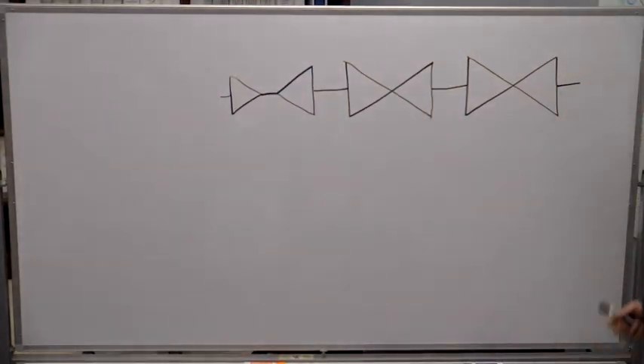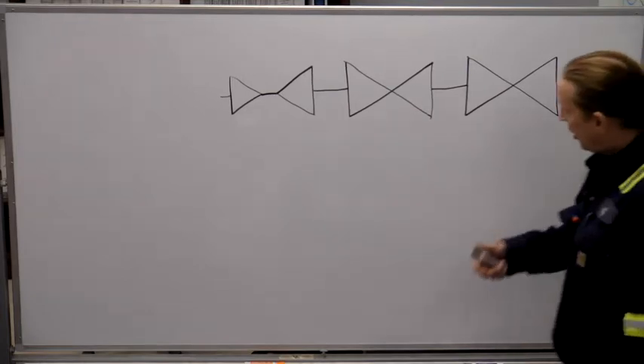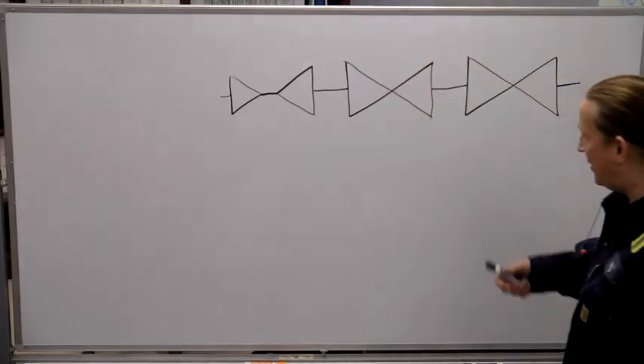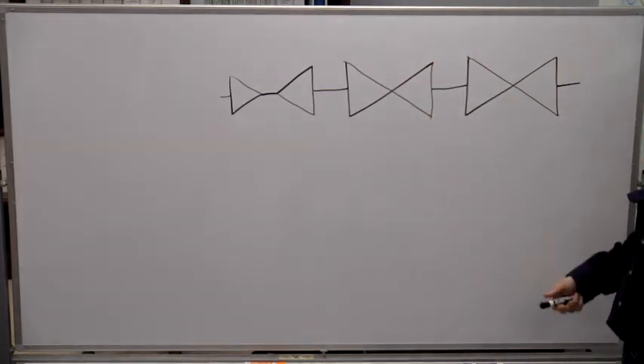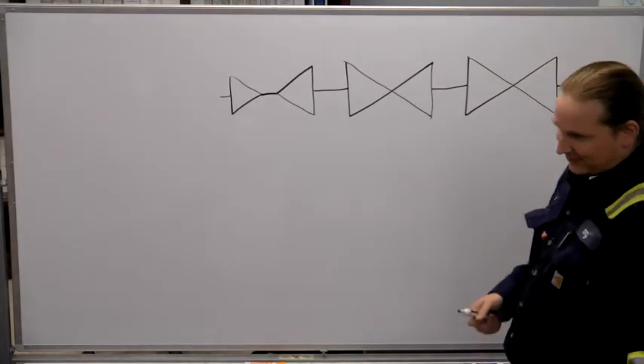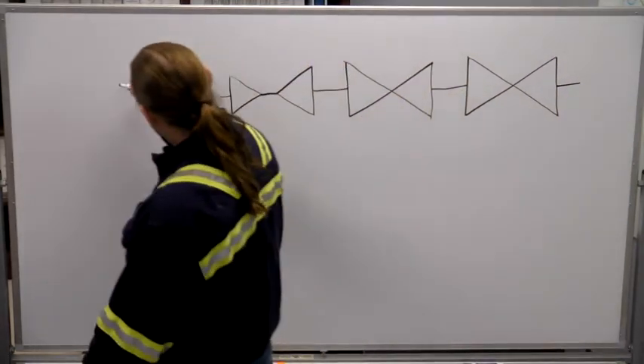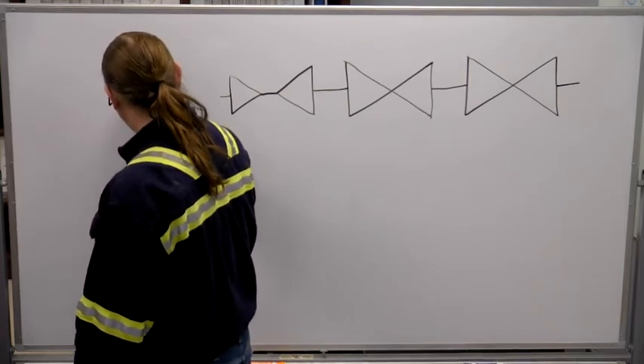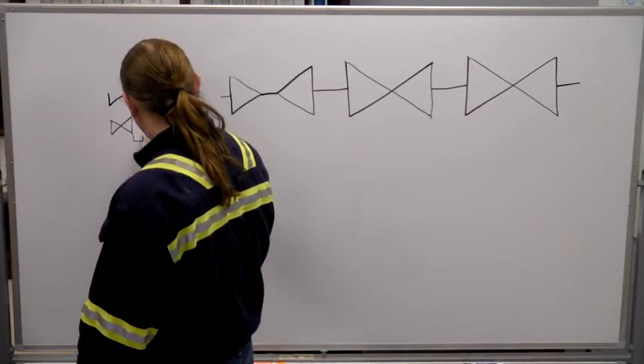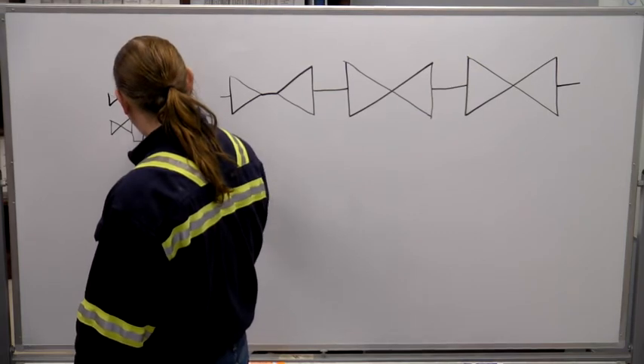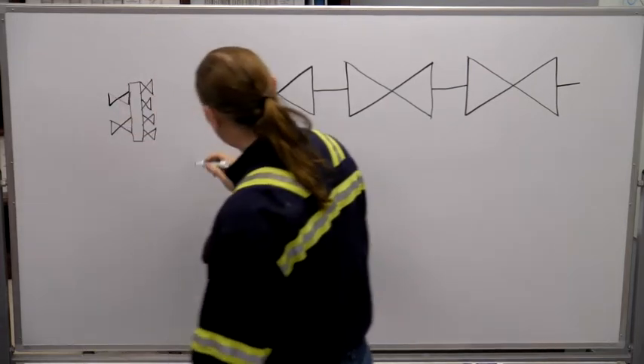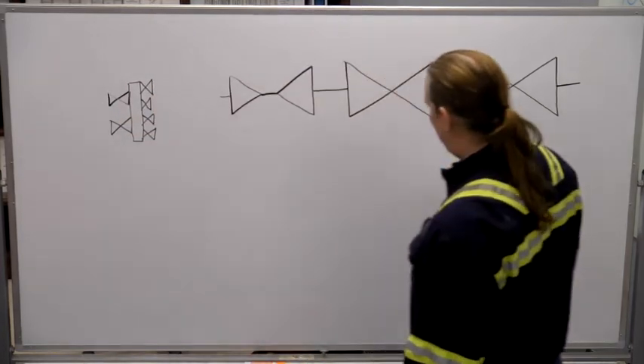Turbine auxiliaries — this overlaps with talking about the turbine itself some. What we're doing now is EHC, which stands for electro-hydraulic control, and it's an oil system. What is it controlling? Steam control valves. So we've got two main steam stop valves, four control valves — flow control valves — and then we have two intercept valves.